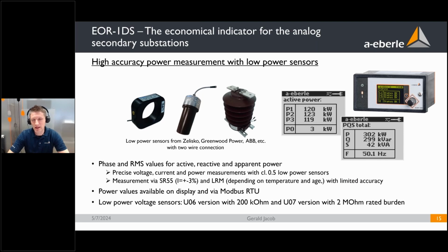These sensors on the last page are not quite precise, but they help you to do easy short circuit and earth fault detection. In addition, our device, and this is a big difference to our competitor devices, is also capable of so-called low power sensors. There are low power sensors from different manufacturers. The most common are from Zelisko, Greenwood Power, ABB, and so on. And these sensors are available with two-wire connections, and these sensors can be connected to an EOR-1DS.